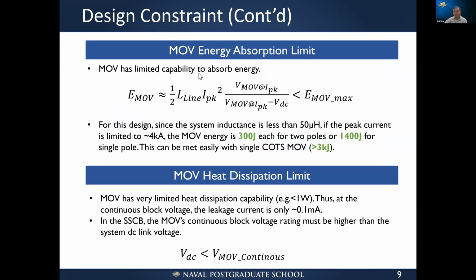And also, we see that the MOV will absorb energy, and the MOV, of course, has a limited capability to absorb energy. So the energy absorbed in the MOV can be estimated with these equations. We'll not go into the details, you can find some references, but it is pretty much proportional to the energy stored in the line inductance at peak current. We want to make sure this MOV can handle this.